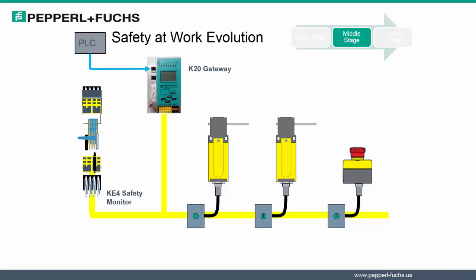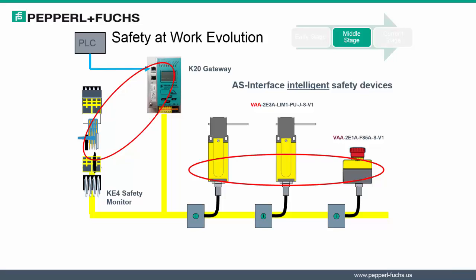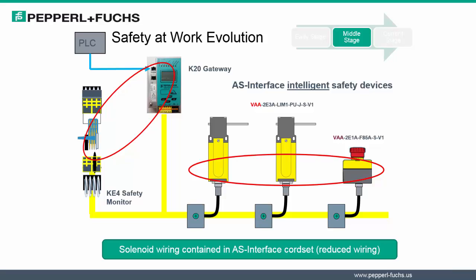Now let's see what changed in the middle stage of this evolution. In the middle stage of the Safety at Work evolution, the AS Interface gateway was still separate from the safety monitor. However, now the devices that were originally non-intelligent safety devices transitioned to intelligent safety devices. Therefore, the devices were addressed and the modules connecting to the AS Interface cable were passive devices and non-addressable. Solenoid wiring was now contained in the cord set, further reducing the wiring of the safety system.